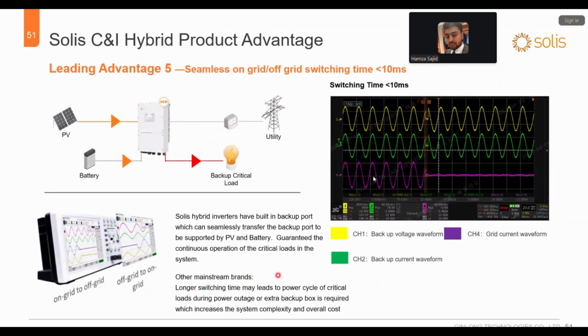Now, this leading function is different from the others, because when you are adding a BESS system, it is by default AC coupled. So if a grid outage happens, it cannot support the load. They need to install a PCS, and they need to install an STS, which has a certain delay for the operations. But in the Solis case, the switching time is less than 10 milliseconds, which is okay for most data centers or banks. It can be utilized there, and actually it is less than 5 milliseconds.